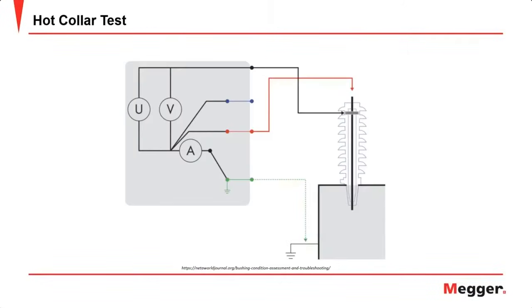Next, we have the hot collar test. This is where we are not using that test tap on the bottom, and instead we are using a conductive rubber collar that you put around the bushing. And this is used to help separate or test bushings that don't have a test tap, or to test bushings more as an investigative step, where you can now separate the bushing itself out into different parts by where you place that hot collar strap.